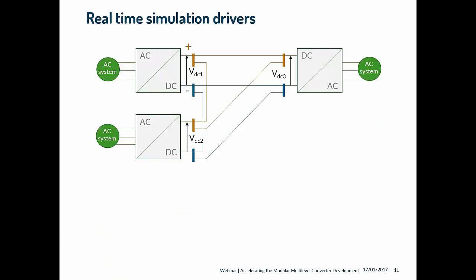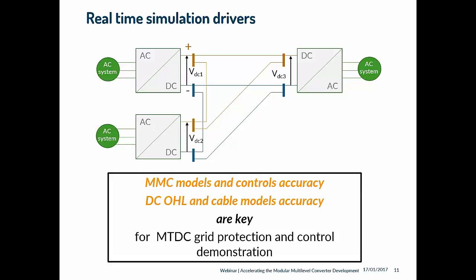So what are the drivers for the real-time simulation of HVDC grids? Here we see a sketch of a 3-terminal HVDC grid composed of interconnected MMC converters. Our study addresses the problem of MTDC grid protection and control, and for those studies to be accurate, it is key that the MMC models and controls, and the DC overhead lines and cable models, are accurate.